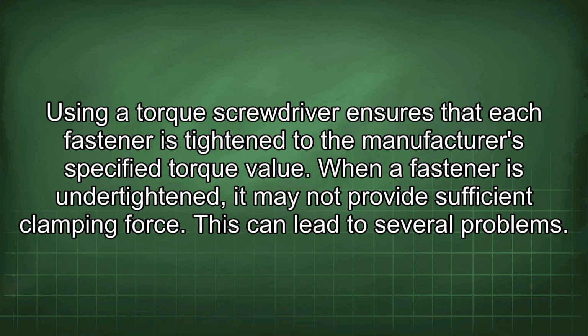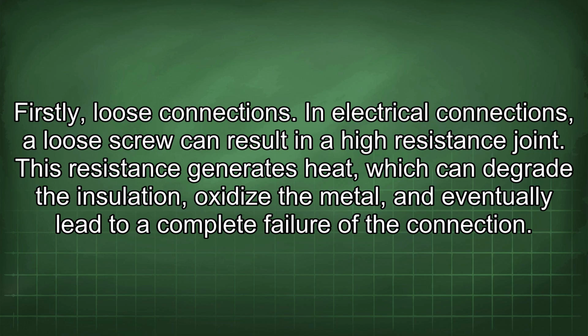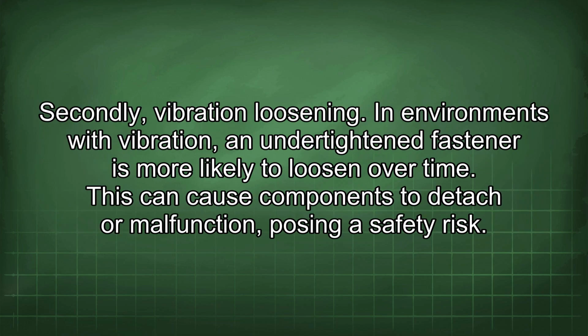When a fastener is under-tightened, it may not provide sufficient clamping force. This can lead to several problems. Firstly, loose connections. In electrical connections, a loose screw can result in a high-resistance joint. This resistance generates heat, which can degrade the insulation, oxidize the metal, and eventually lead to a complete failure of the connection. Secondly, vibration loosening.